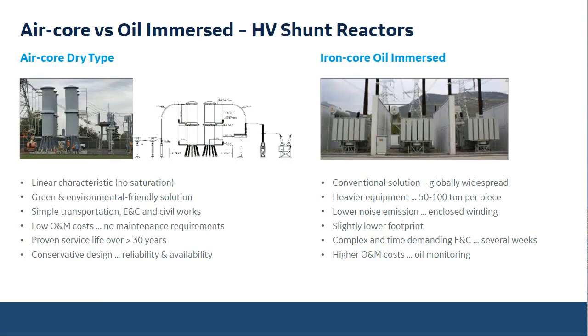I did mention that the oil-filled ones were traditionally applied at extra high voltage levels, and we've been seeing more and more air-core dry type being used. The reason for that is, first, the dry type air core does not have oil, so there are no issues in terms of environmental risk or impact in terms of fire and explosion. It's a very simple technology, very easy to install, basically placing coils on top of insulators and connecting terminals.